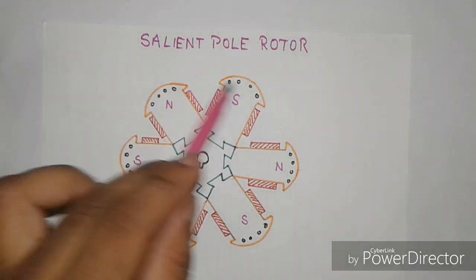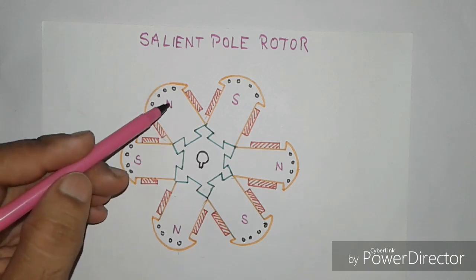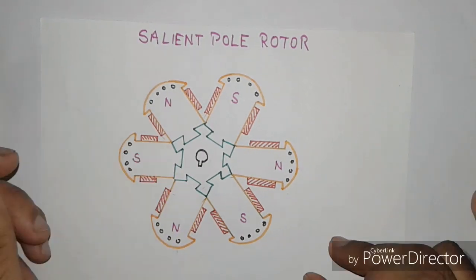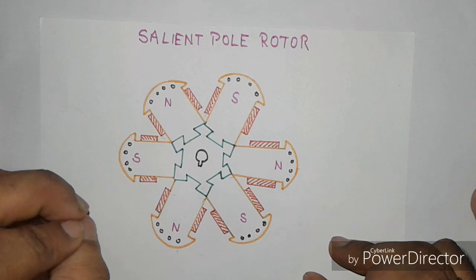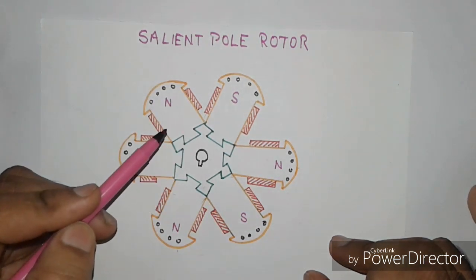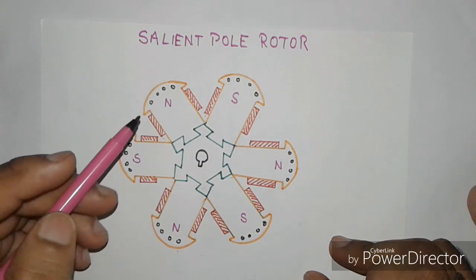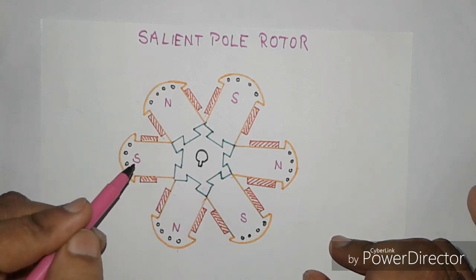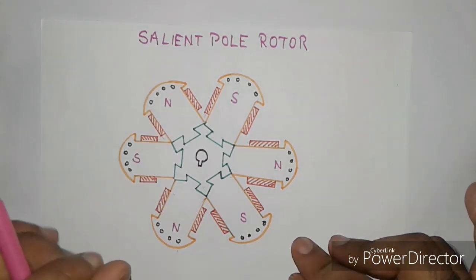These types of rotors are used for medium speed and low speed alternators. These poles are projected out from the surface of the rotor core. These projected poles are made up of steel lamination to reduce eddy current losses. In these rotors, the poles are fitted by dovetail joints to a spider keyed to the shaft. The diameter of these rotors is larger and the length is small.